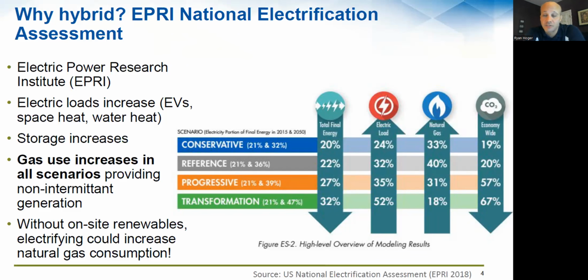But the other thing is, as you guys know, the peak usage for almost all power plants, at least in the northern half of the country, is going to be in the summertime, right? July, August, that's the peak usage. Every building's running their AC, every homeowner's running their AC, right? And all the baseline stuff didn't change: water heating, lighting, computers, all that stuff. So the grid, the network of wires throughout the country, state, area, region, all the wires are sized based on a certain amount of amp flow through them. And that's based on these worst case summer days, plus, hopefully, some buffering capacity, right?